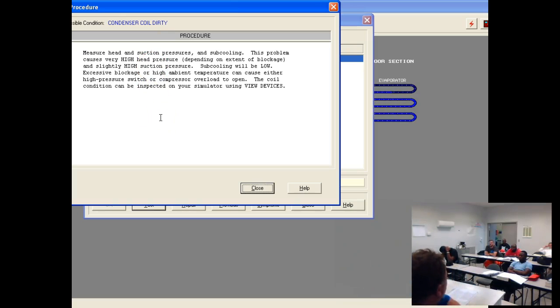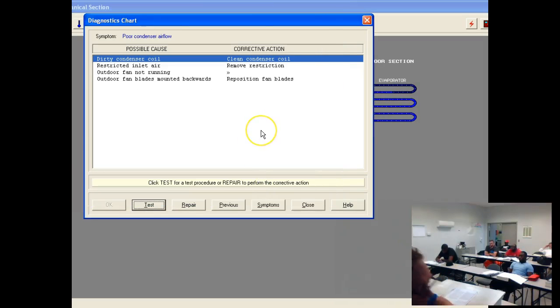Do we have high head pressure? No, we had low head pressure. So that's probably a good giveaway. Now we could have taken subcooling, right? Because you've got a thermometer. Subcooling would be low. The coil condition can be inspected by looking at it, right? And so there is no point in me repairing that because it's not a dirty condenser coil. And if you do it, it's going to show up on what you did.